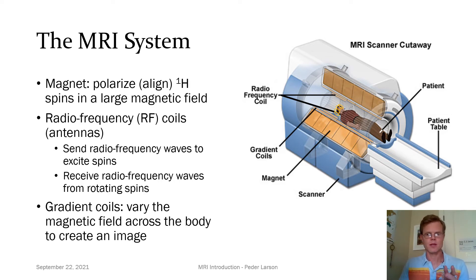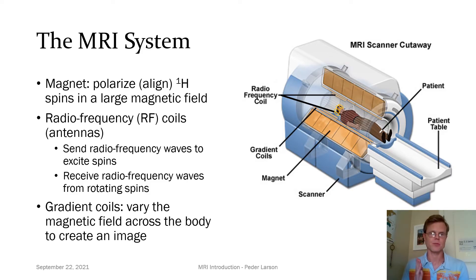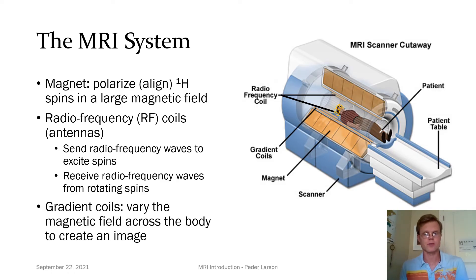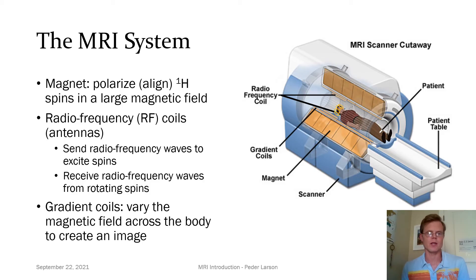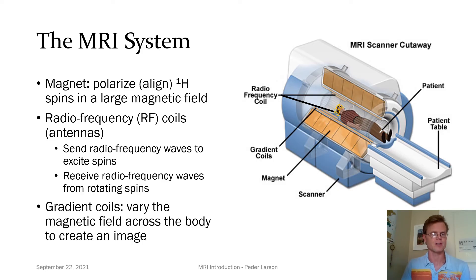To summarize, I want to show what is inside of an MRI system. The majority of the real estate inside an MRI scanner is devoted to the magnet, whose purpose is to polarize or align our hydrogen spins in a large magnetic field. Then we have sets of radio frequency coils, which are antennas, and their purpose is twofold: one is to send in the radio frequency waves to excite our spins, and the other is to receive the radio frequency waves that come back from these rotating spins. And finally, we have our gradient coils, whose purpose is for imaging — they vary the magnetic field across the body, creating different frequencies that we can separate from our MRI signal to create an image.